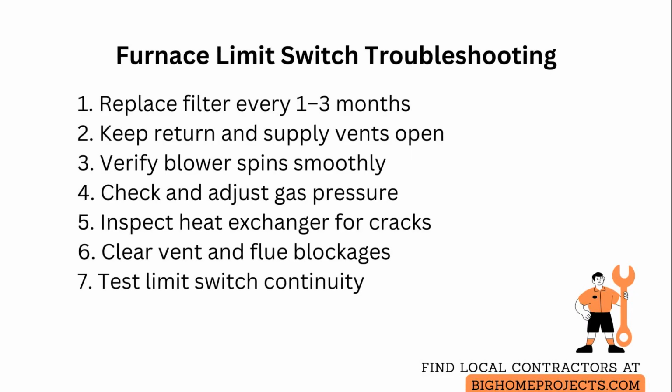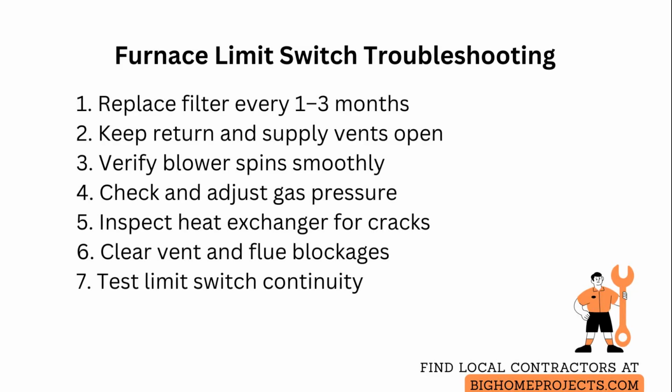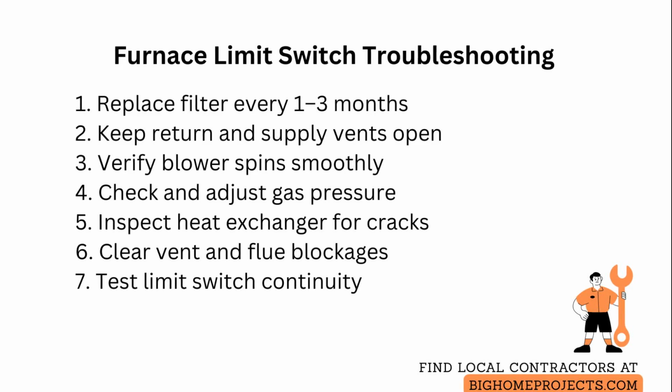A cracked or deteriorating heat exchanger can create abnormal temperature patterns and requires immediate repair or replacement because it can also allow combustion gases into the cabinet. Look for rust, visible cracks, or soot and prioritize a heat exchanger inspection.